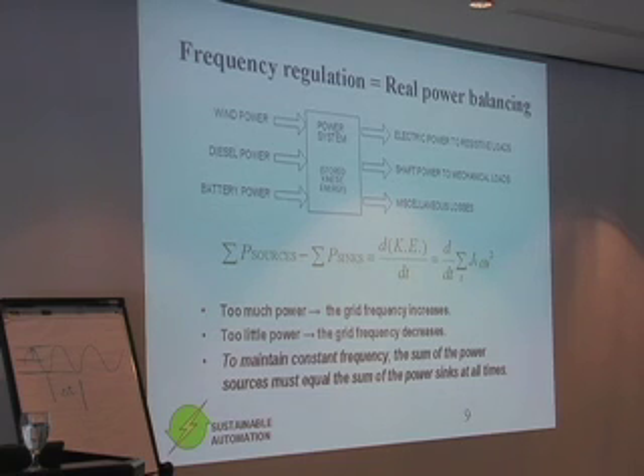Frequency regulation is essentially a problem of making sure on an instantaneous basis all the real power sources equal all the real power sinks. If there's an imbalance between the sources and sinks, the system will speed up, or it will slow down if you're taking out more power than you're putting in.